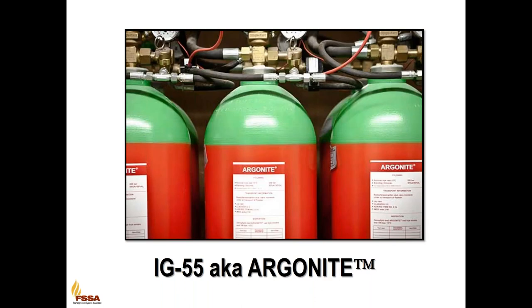IG55, also known as Argonite, is a simple blend of 50% argon and 50% nitrogen, with a density similar to that of air. Both argon and nitrogen are clean, naturally occurring gases that are readily available throughout the world. The agent has no global warming potential or ozone depletion potential. Argonite requires no post-fire cleanup and will not decompose or produce any byproducts when exposed to flame from a fire situation.